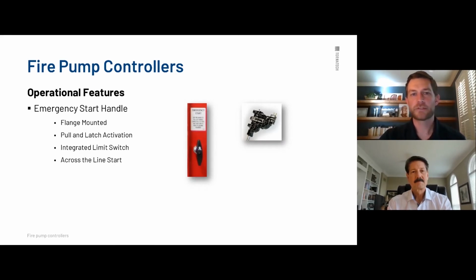We're all required to have an emergency start handle, and this is in general for all fire pump controller manufacturers. Ours is one that you have to pull out and pull and latch to keep it in place. One thing to note when you're using the emergency handle is that it has an integrated limit switch. The idea with the emergency handle is to pull it and not be too gingerly with it. Just pull it and lock it in place. You don't want to feather it. If it's an emergency start, you just need to pull it and lock it.